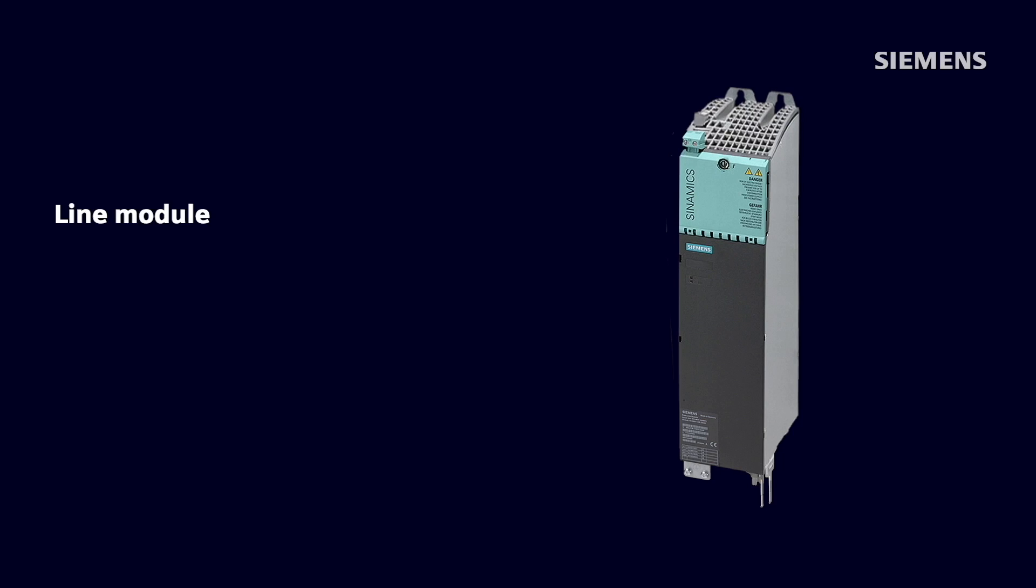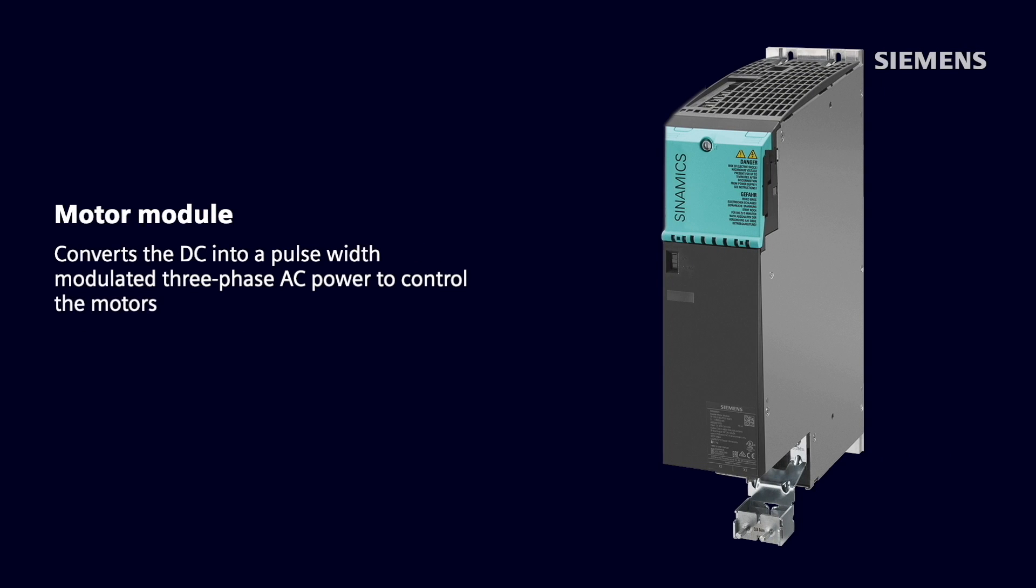Next is the line module, which is the subject of this video. The main function of the line module is to convert the three-phase AC power into a common DC bus supply, which feeds the motor module inverters. The motor modules then convert the DC into a pulse-width modulated three-phase AC power to control the motors. An additional function that the line module serves is that it also provides an indicator for the motor modules that the DC link is powered up and ready to feed the motor power.